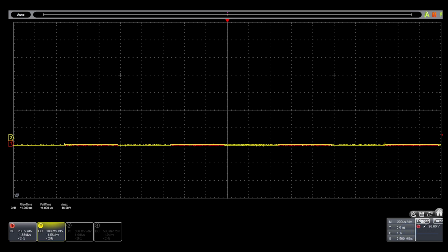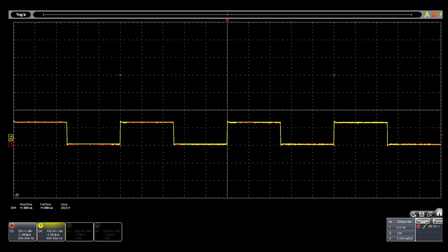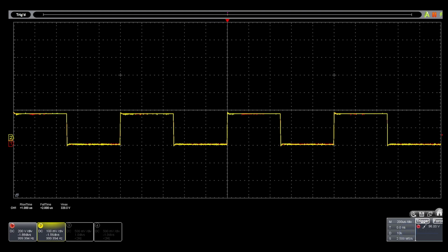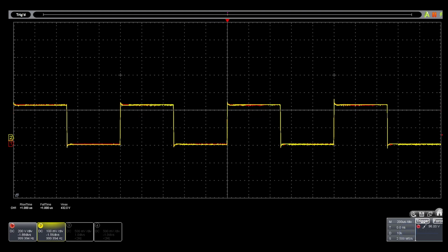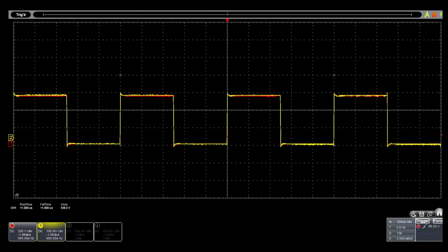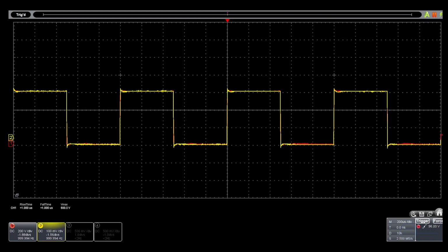So right now I'm going to start the ramp, and you can see the main output is in red, and I'm putting the voltage monitor into channel 2, shown here in yellow. As they ramp up, they're virtually identical, even sharing a lot of the same features. You can still see the same overshoot and the same aberrations. So it's really a voltage monitor that you can trust.